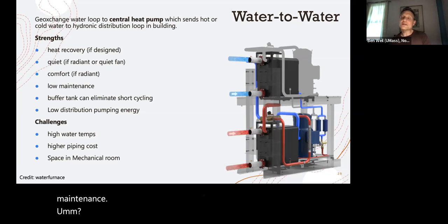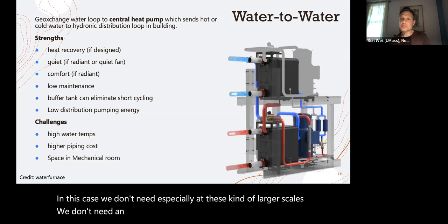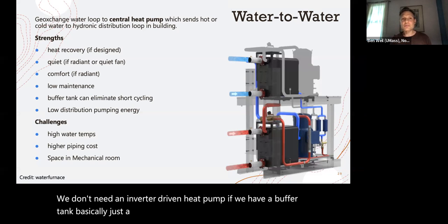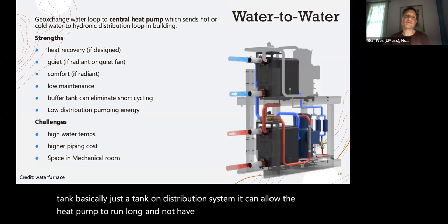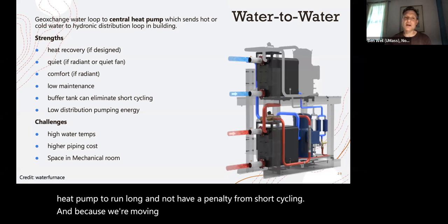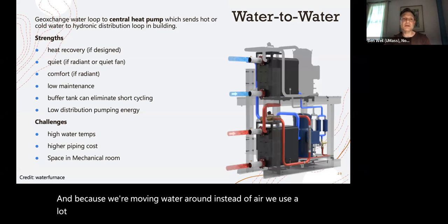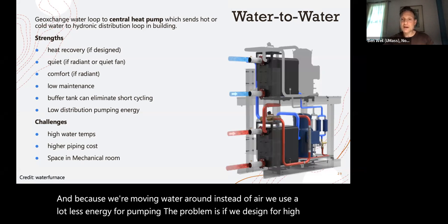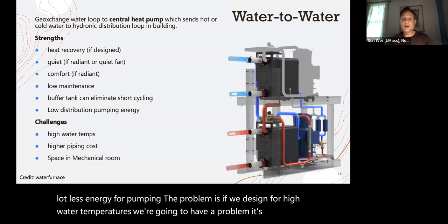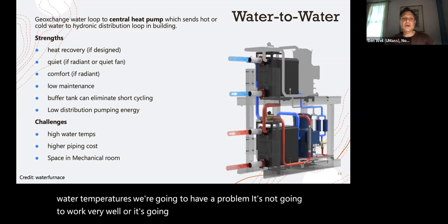In this case, especially at these larger scales, we don't need an inverter-driven heat pump if we have a buffer tank, basically just a tank on the distribution system. It can allow the heat pump to run long and not have a penalty from short cycling. And because we're moving water around instead of air, we use a lot less energy for pumping. The problem is, if we design for high water temperatures, it's not going to work very well, or it's going to be inefficient.